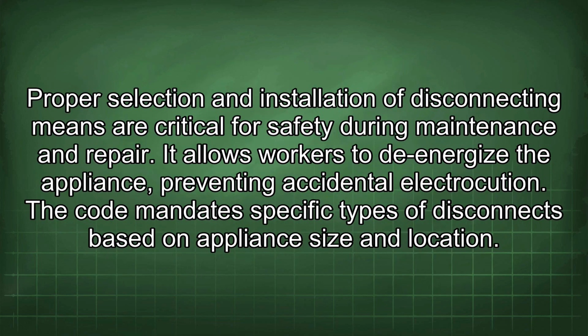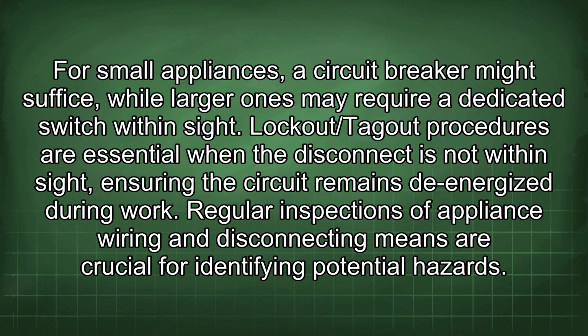Proper selection and installation of disconnecting means are critical for safety during maintenance and repair. It allows workers to de-energize the appliance, preventing accidental electrocution. The code mandates specific types of disconnects based on appliance size and location. For small appliances, a circuit breaker might suffice, while larger ones may require a dedicated switch within sight. Lockout/tagout procedures are essential when the disconnect is not within sight, ensuring the circuit remains de-energized during work.